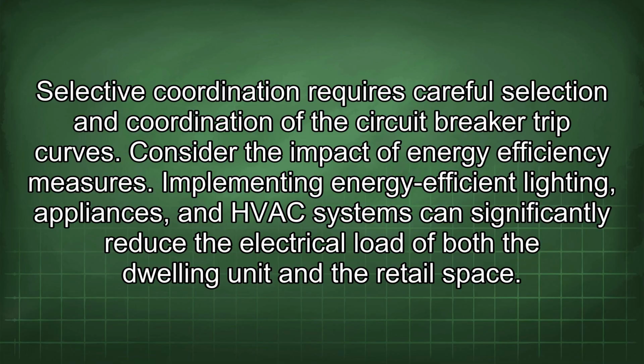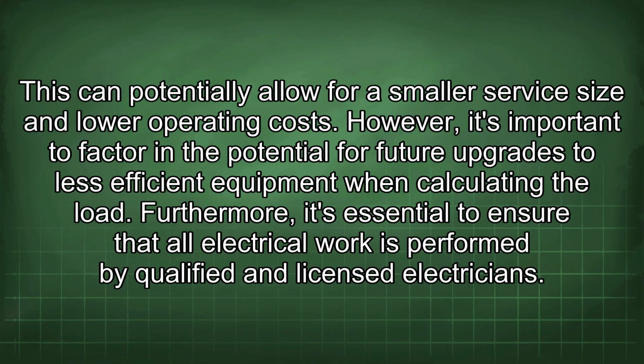Consider the impact of energy efficiency measures. Implementing energy-efficient lighting, appliances, and HVAC systems can significantly reduce the electrical load of both the dwelling unit and the retail space. This can potentially allow for a smaller service size and lower operating costs. However, it's important to factor in the potential for future upgrades to less efficient equipment when calculating the load.